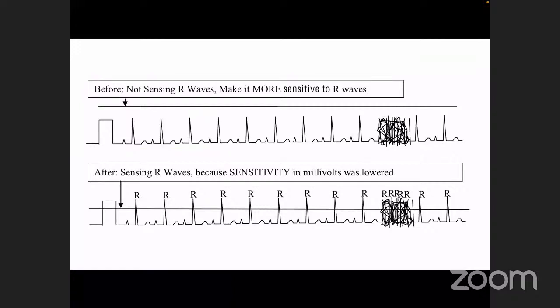When the device detects an R, when it sees the voltage that it's received from the heart, you typically see R waves or P waves, depending on what you're trying to sense. For example, let's take R wave as an example. The R wave will go up to a certain limit or voltage, and then obviously will go down, and that's seen in the ECG to make it easier.